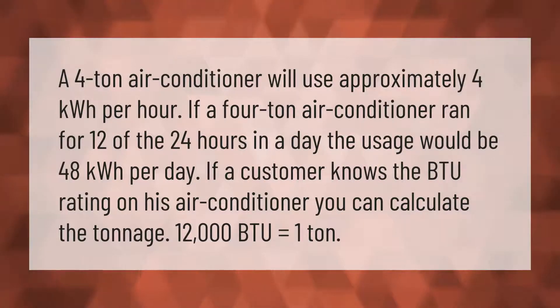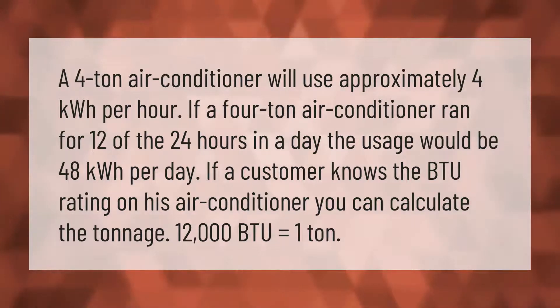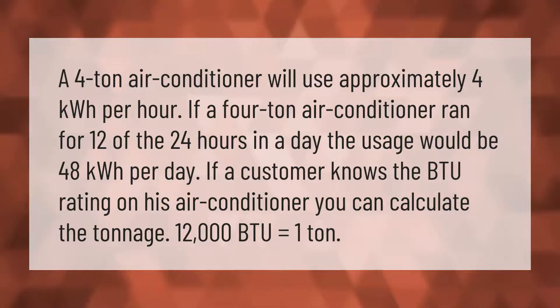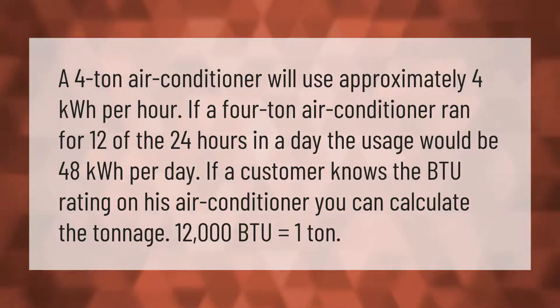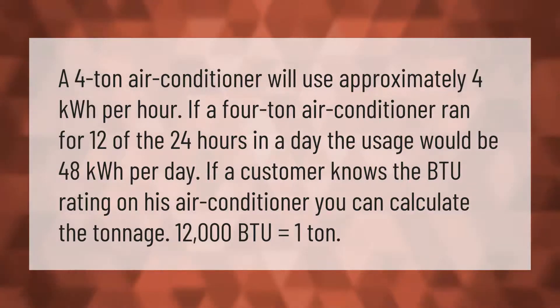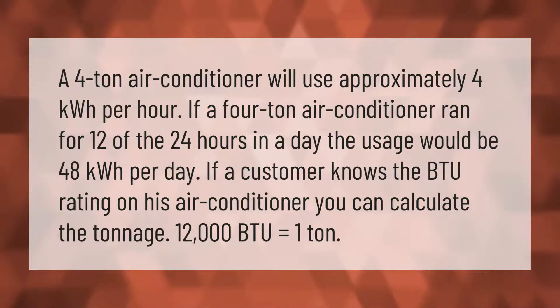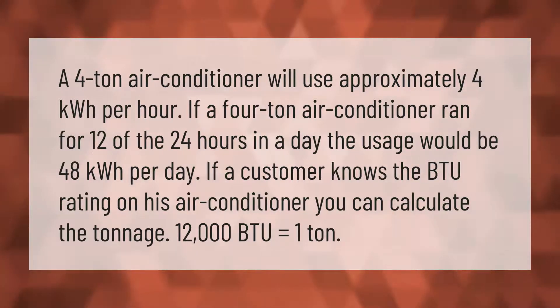A four-ton air conditioner will use approximately four kilowatt-hours per hour. If a four-ton air conditioner ran for 12 of the 24 hours in a day, the usage would be 48 kilowatt-hours per day. If a customer knows the BTU rating on his air conditioner, you can calculate the tonnage — 12,000 BTU equals one ton.